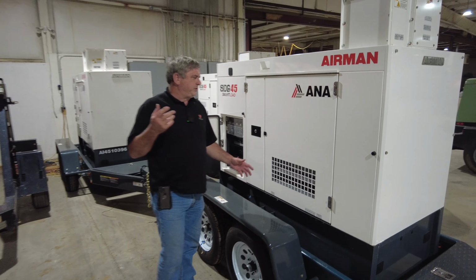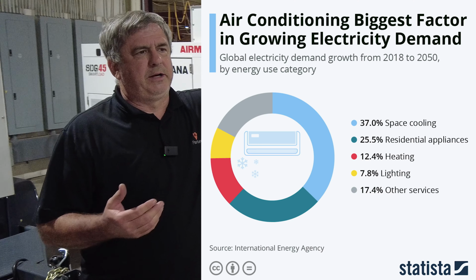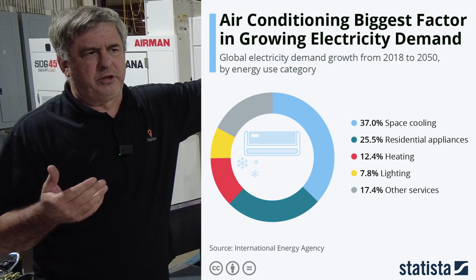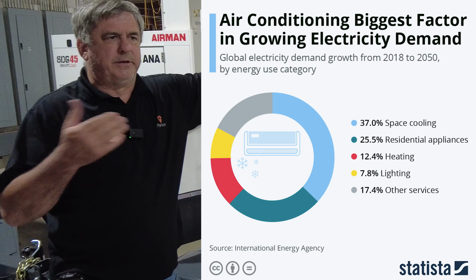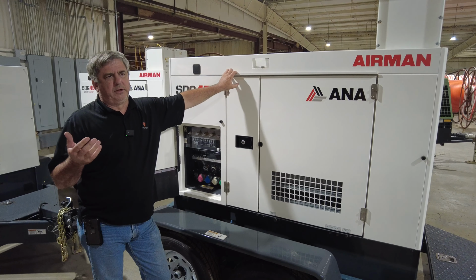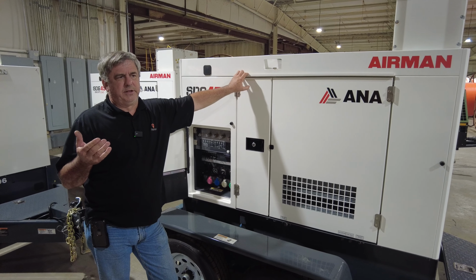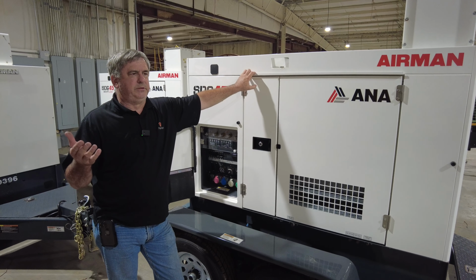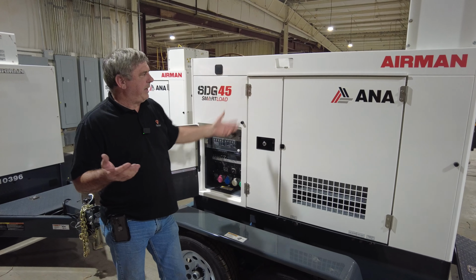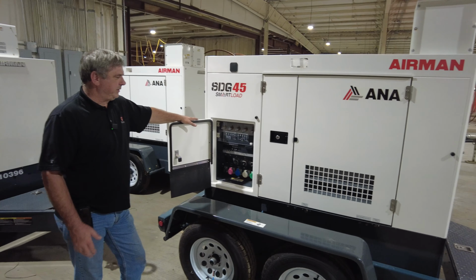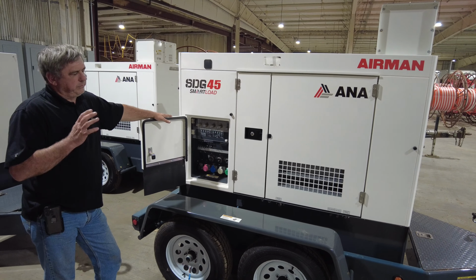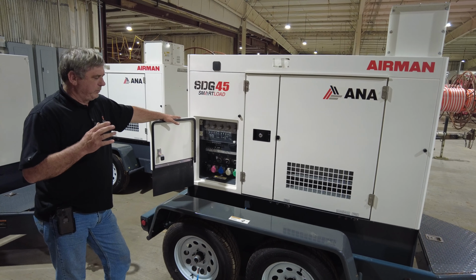If you're interested in a generator for your home, air conditioning is going to be your largest load, or your heating load if you have a heat pump. If you had a larger home, you might need a 30, 40, or 50 kW generator. Standing behind me is a 45 kVA generator, so about 35 kW. For most homes, this size generator would be really nice.